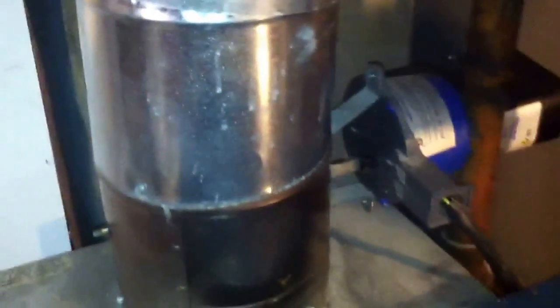I'm going to do a little heat check on a steam boiler. It's a Utica. It's got a low water cutoff and an automatic feed — no bypass, but that's the way somebody set it up. Electronic ignition with a flue damper, automatic damper.